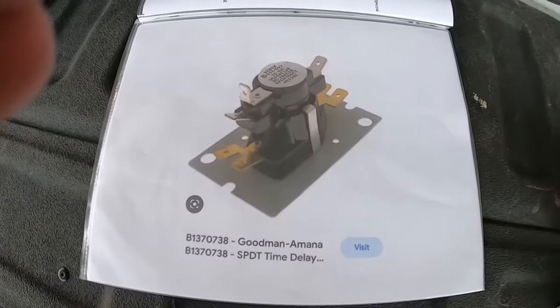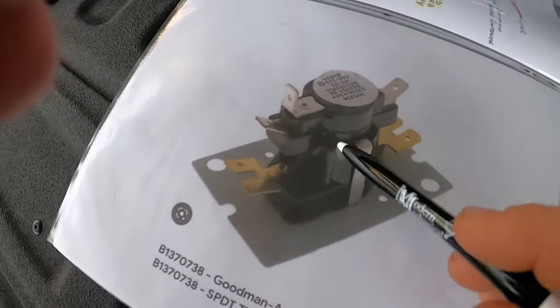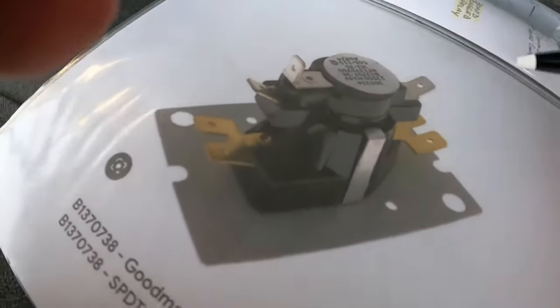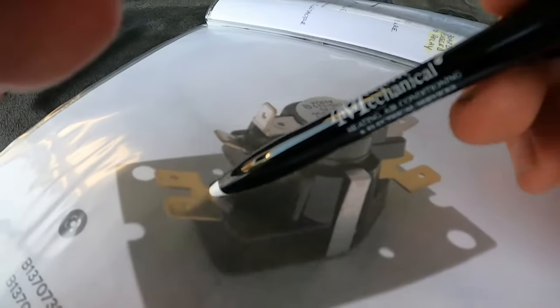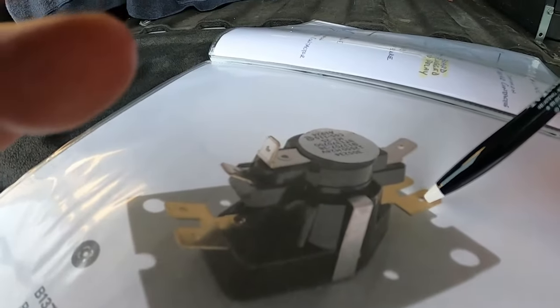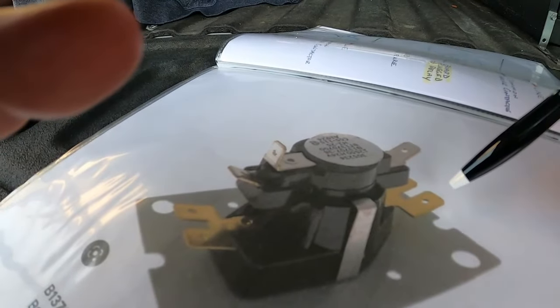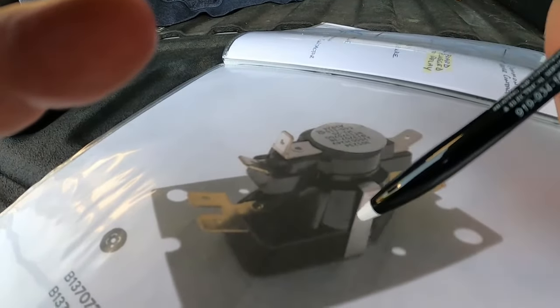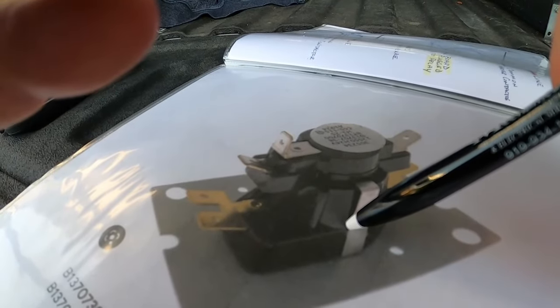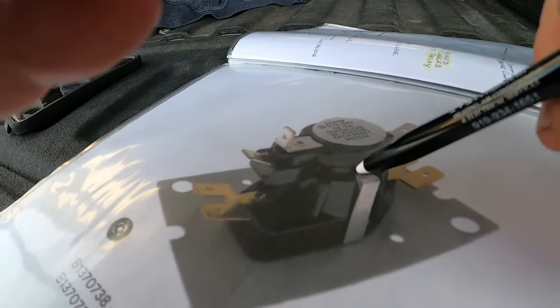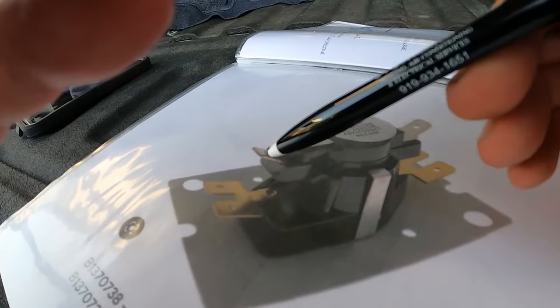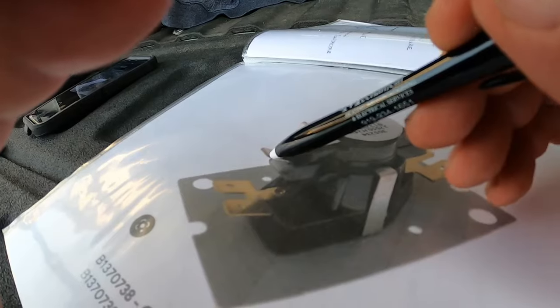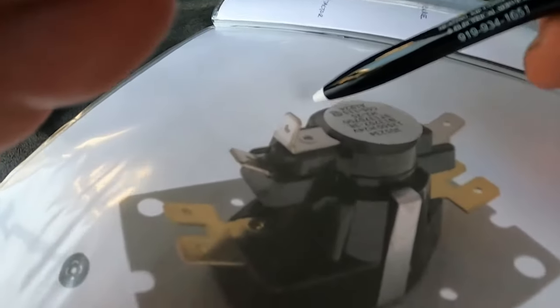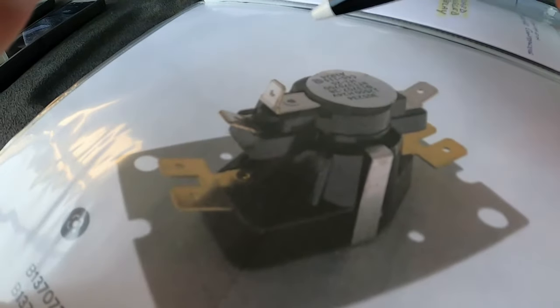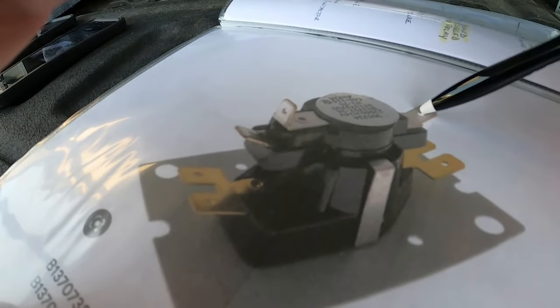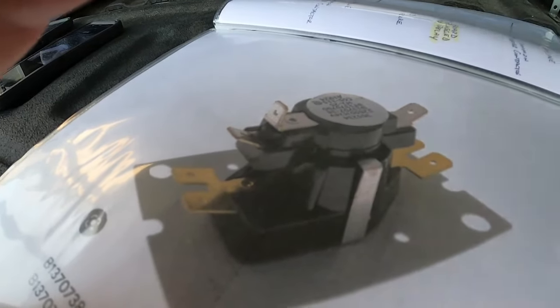Goodman, Amana air handlers, heat pumps, older ones that used this time delay sequencer for their blower. You had your low voltage on the bottom, your common. Your G would go over here, or vice versa. Doesn't matter, as long as it's got a common and a G. Then you've got your thermal disc that eventually will warm up, pop, raise that rod in the center, and close the switch. Your blower speed was here, your common, because this is a normally closed switch between this terminal and that terminal. It's normally closed. Your line voltage in to power your blower would connect to there.